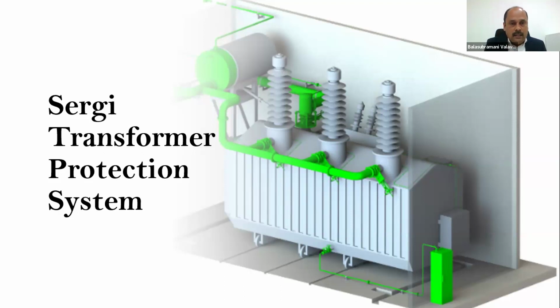What happens is, when the arc happens, it travels very fast, in less than 10 milliseconds. It develops dynamic pressure. The electric arc can occur and turn into dynamic pressure, and subsequently it touches the wall of the particular item. If it is the transformer tank, it touches the wall, and then static pressure increases. The moment that static pressure increases, if there is no SERGI system, it will lead to an explosion. There are cases where actual explosions have happened without this particular SERGI system.